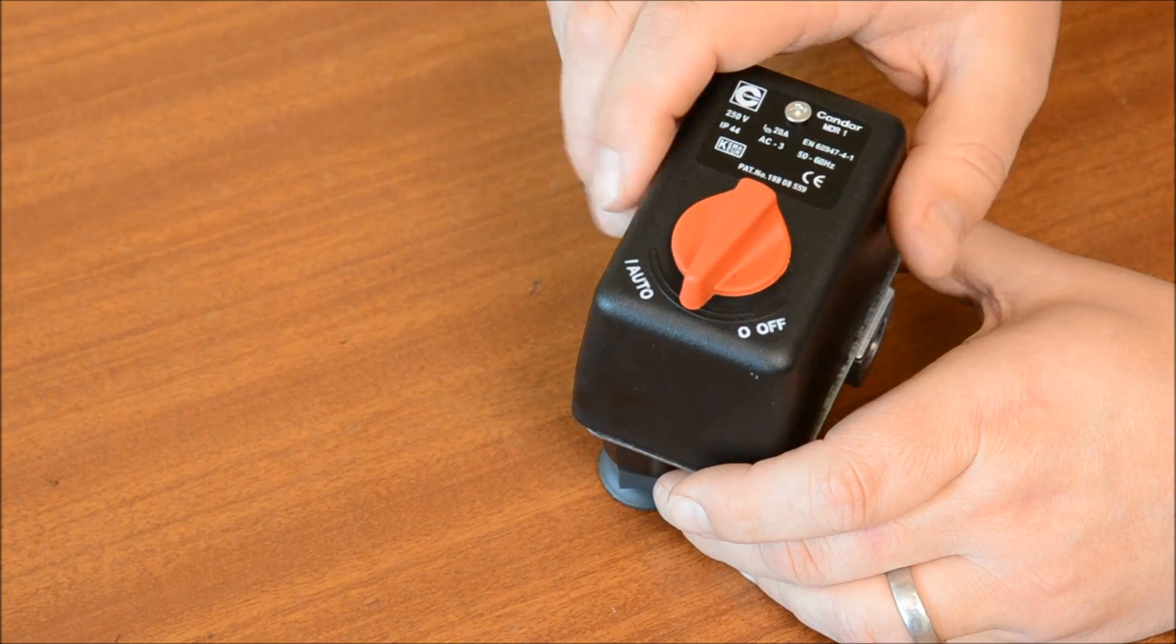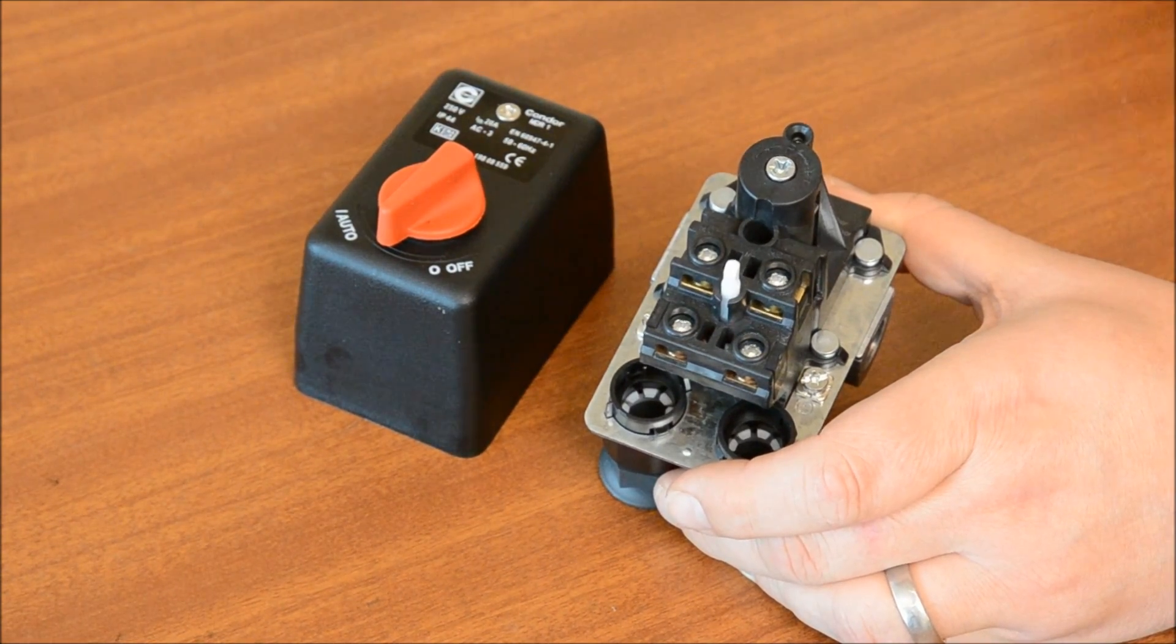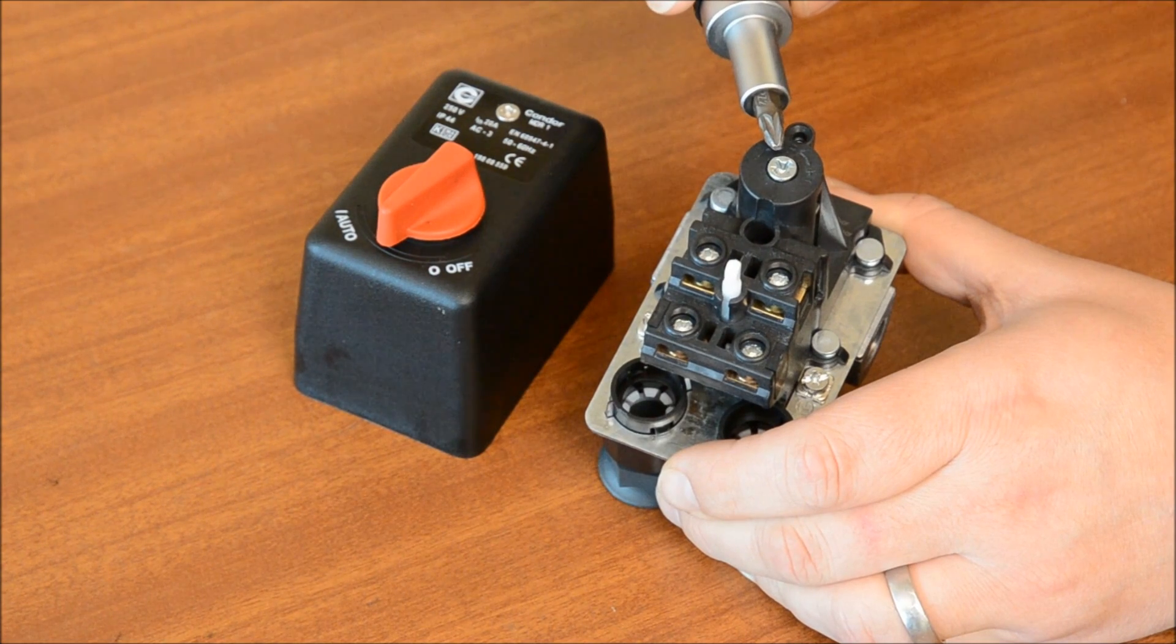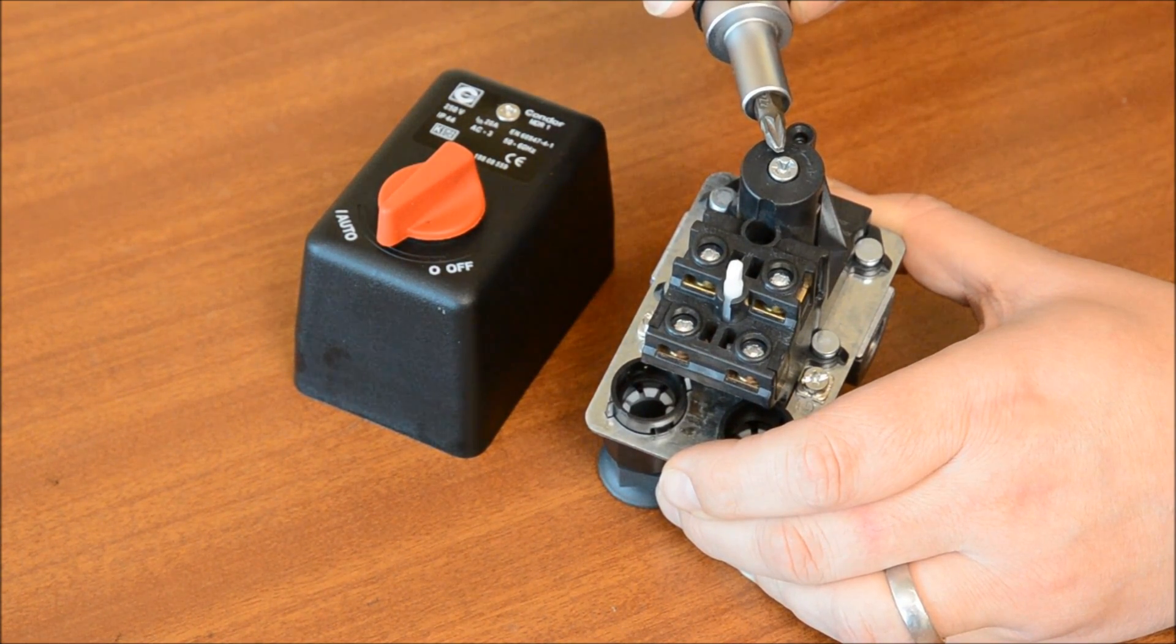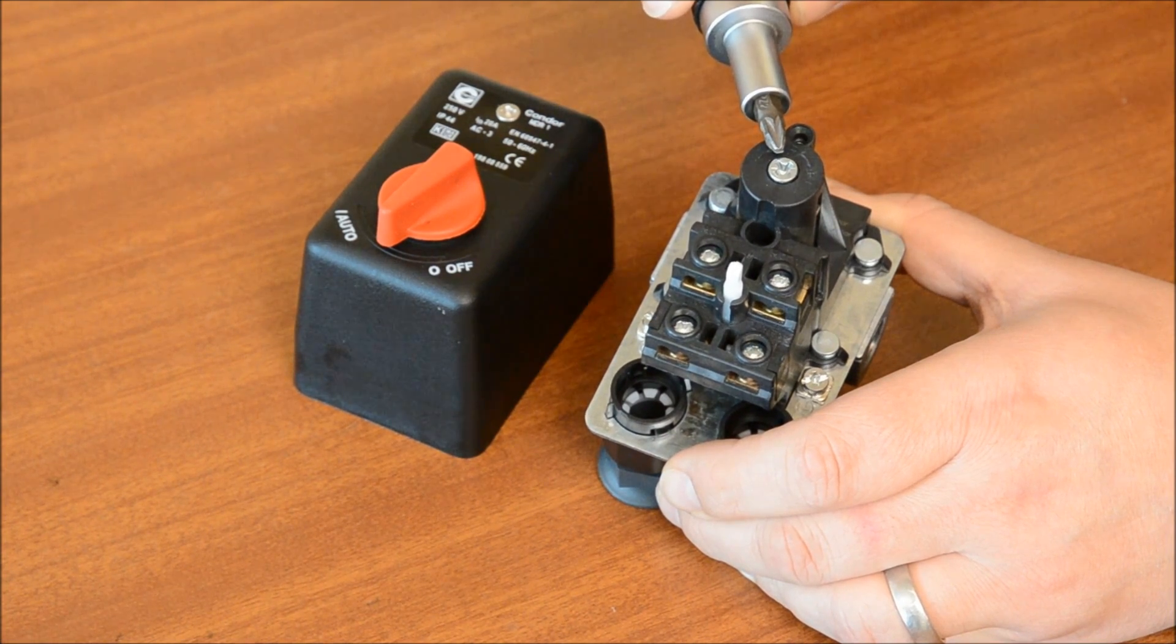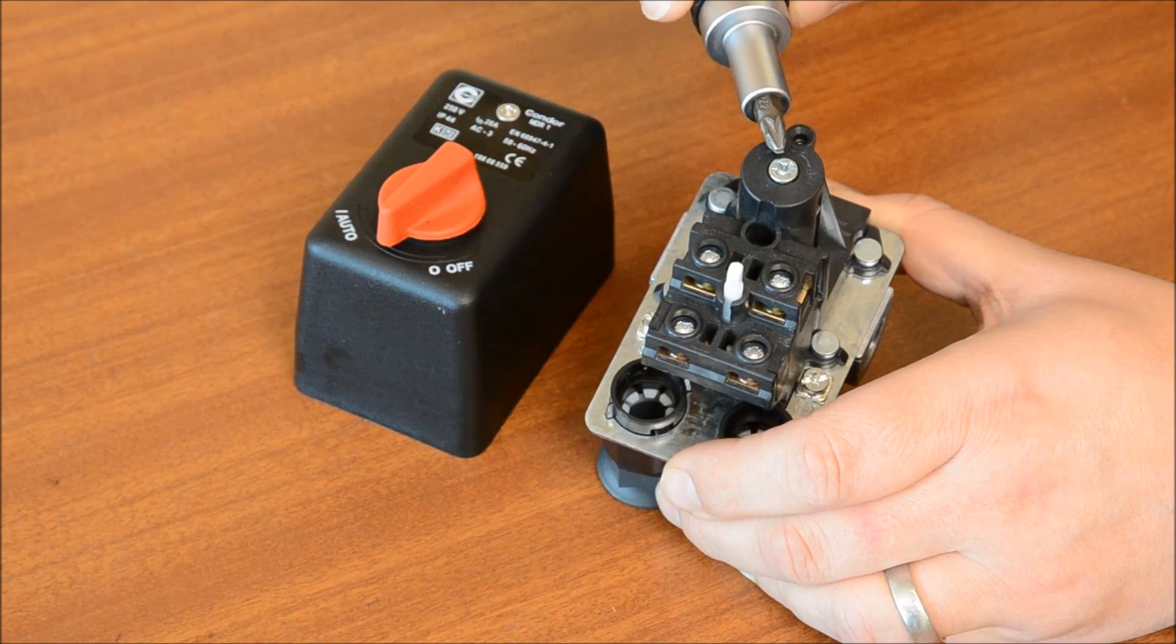The switching pressure can be adjusted by turning the main calibration screw clockwise to increase the cut-in and cut-out pressure, and counterclockwise to decrease the cut-in and cut-out pressure. The difference between the cut-in and cut-out pressure is fixed.